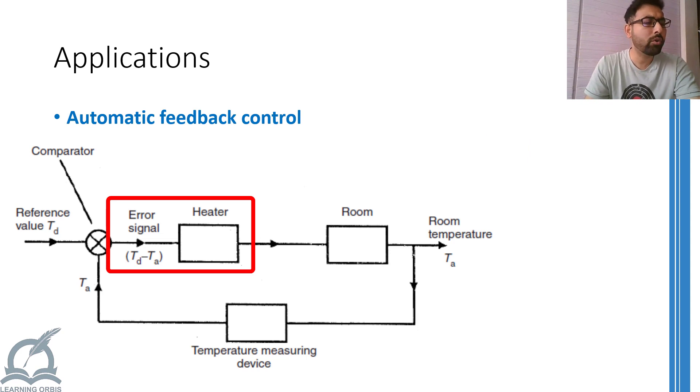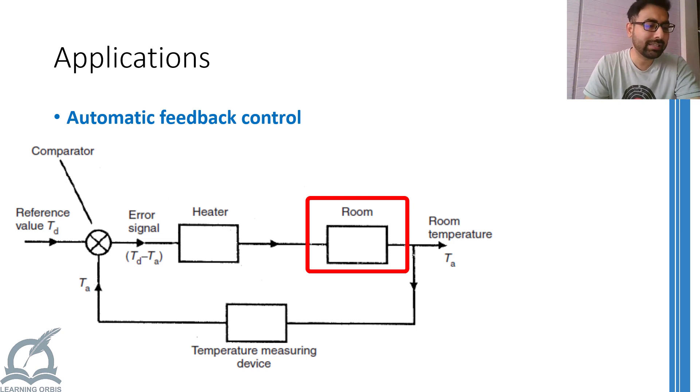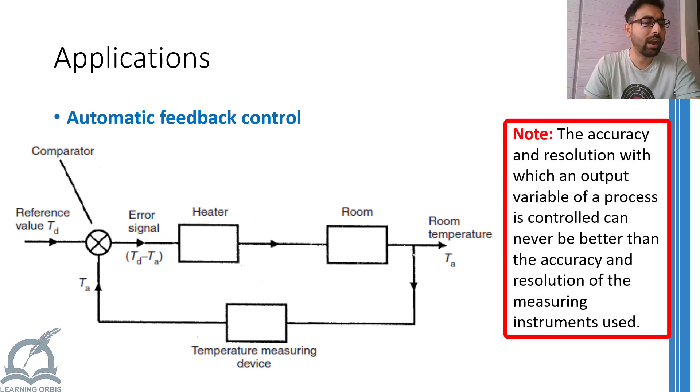This on-off or more practically tripping off heater will continue for as long as you leave the heater on and the temperature of the room will keep on fluctuating around 26 degrees Celsius. One thing to notice over here is that the amount of fluctuations around your set temperature will depend on a number of factors out of which the accuracy and resolution of the temperature sensor would be the most important.